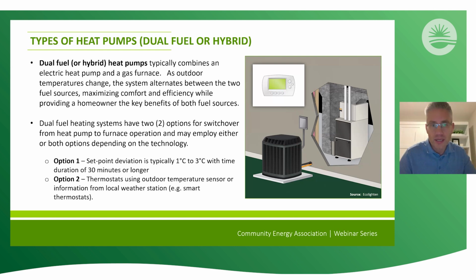So the first one is it'll have what's called a deviation from the set point in the house, which can be anywhere from 1 degree to 3 degrees Celsius. And if the heat pump is not able to hit that set point within a certain amount of time, it'll recognize that it can't keep up, and it'll switch over to the gas furnace. And then the other technology from a control standpoint that it'll employ is a temperature sensor.